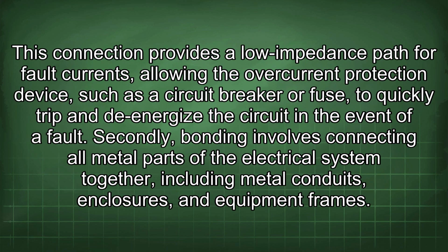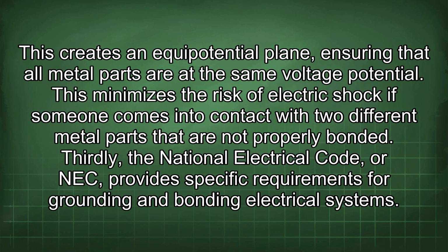This connection provides a low impedance path for fault currents, allowing the overcurrent protection device, such as a circuit breaker or fuse, to quickly trip and de-energize the circuit in the event of a fault. Secondly, bonding involves connecting all metal parts of the electrical system together, including metal conduits, enclosures, and equipment frames. This creates an equipotential plane, ensuring that all metal parts are at the same voltage potential.